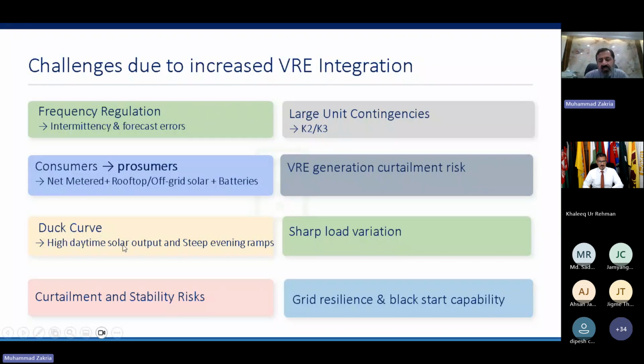What we are doing is ramping down all generators to their minimum level, and most of them we shut down. We have no ramp-down quantum in the high water season - this is the peak water season, and hydel generation is at its peak, so no regulation is available at hydel sites. So we keep the generators off, and then in the evening we have to start them again - combined cycle or other generators. That is an issue. We have tracked the total number of available starts and stops in the year for these generators.